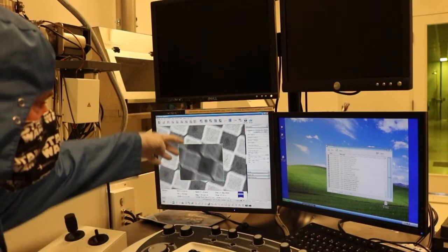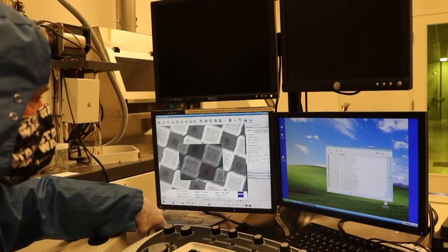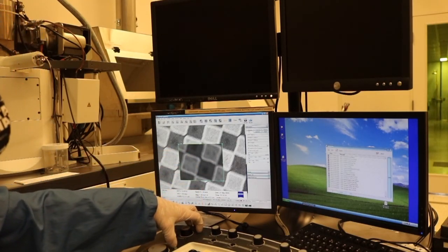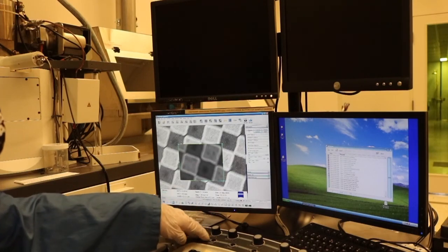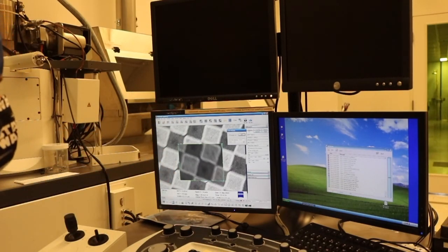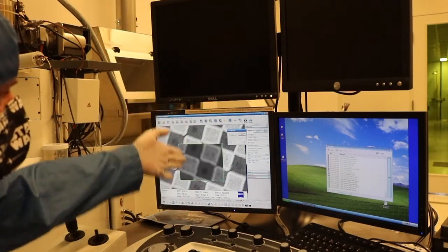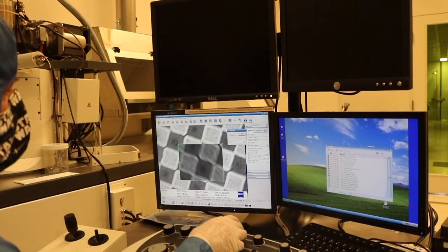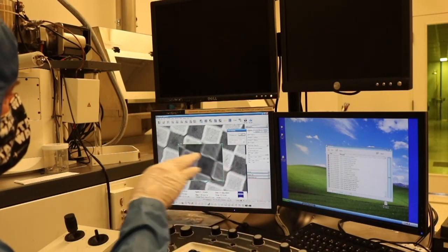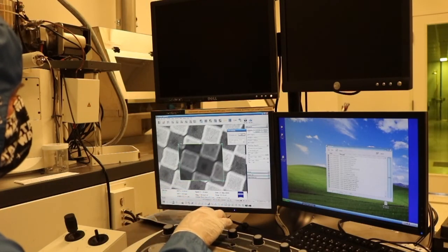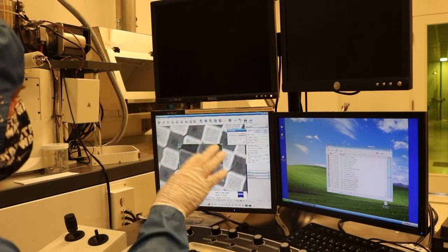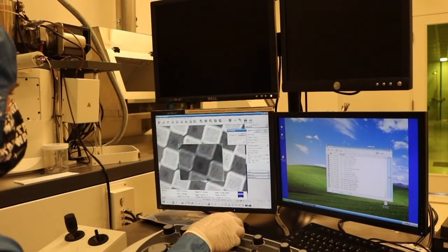So we're just watching for any shift or translation in the image. If you do notice that there is some stretching in this image, that stretching is actually astigmatism. We'll correct the astigmatism after we correct the aperture misalignment. We'll press the wobble button, which is automatically changing the focus for us. As you can see, the image is primarily shifting in the y-axis, so we'll adjust the y-axis. And now the image is shifting left to right, so we'll adjust the x. And basically, we want this to go perfectly in and out of focus until we've got it completed.